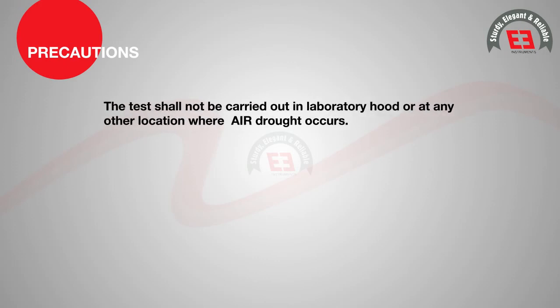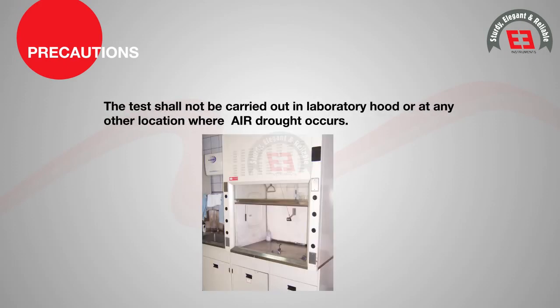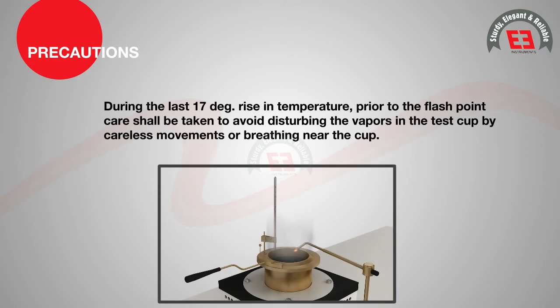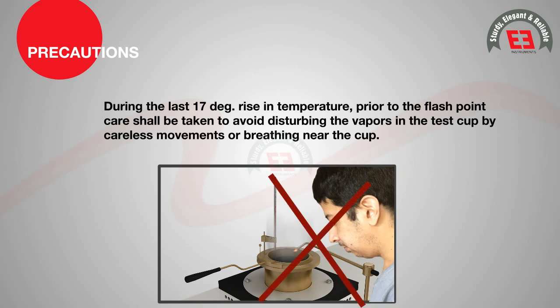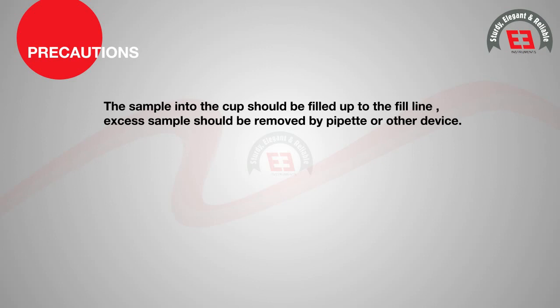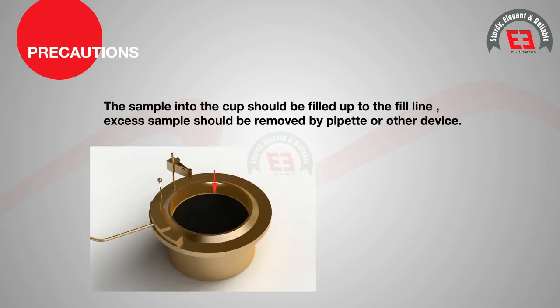Precautions. The test shall not be carried out in a laboratory hood or at any other location where air draught occurs. During the last 17 degrees rise in temperature prior to the flash point, care shall be taken to avoid disturbing the vapours in the test cup by careless movements or breathing near the cup. The sample in the cup should be filled up to the fill line.